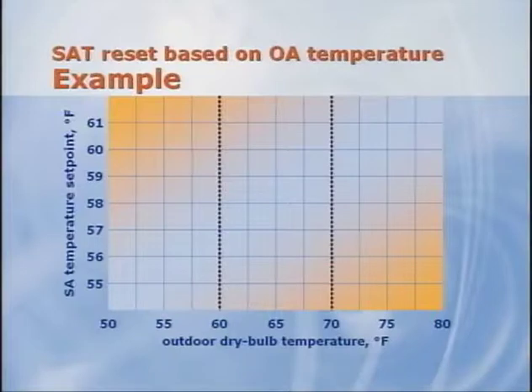These competing issues are often best balanced by first reducing supply airflow, taking advantage of the significant energy savings from unloading the fan. Then, after fan airflow has been reduced, raise the supply air temperature to enhance the benefit of the air side economizer and minimize reheat energy. This slide shows an example of a simple supply air reset strategy that is based on outdoor temperature. When the outdoor dry bulb temperature is warmer than 70 degrees, no reset takes place, and the supply air set point remains at its design value of 55 degrees.